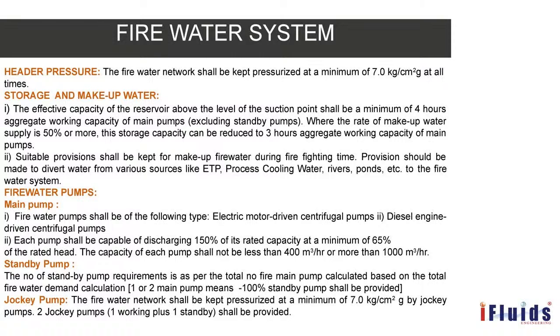fire water network shall be kept pressurized at a minimum of 7 kg per centimeter square gauge. This is the main objective of the jockey pump, and this jockey pump will ensure this particular pressure. So it is required to provide one or otherwise one plus standby jockey pump.